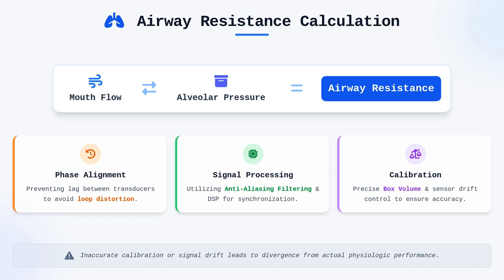When we transition to the calculation of airway resistance, the complexity of signal processing becomes even more pronounced. Airway resistance requires measuring the relationship between flow at the mouth and the alveolar pressure changes derived from the box pressure. One of the major technical hurdles here is the phase alignment between the flow transducer and the box pressure transducer, as any lag between these two channels will distort the resulting pressure flow loop.